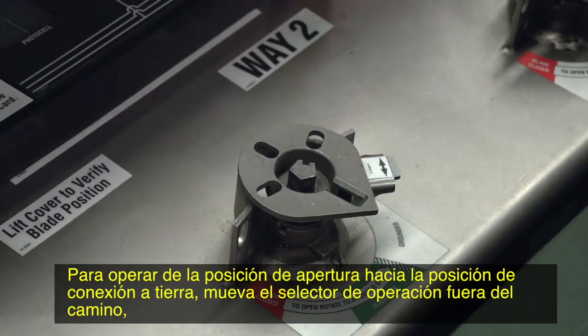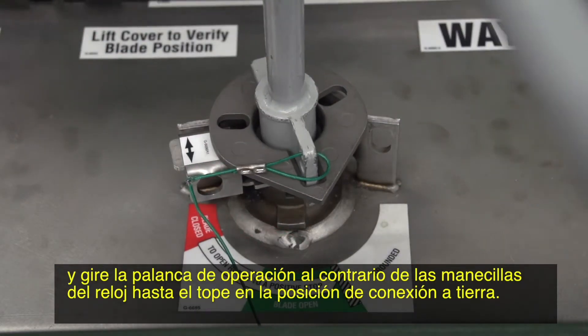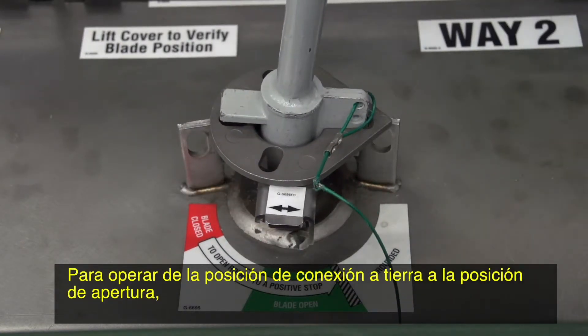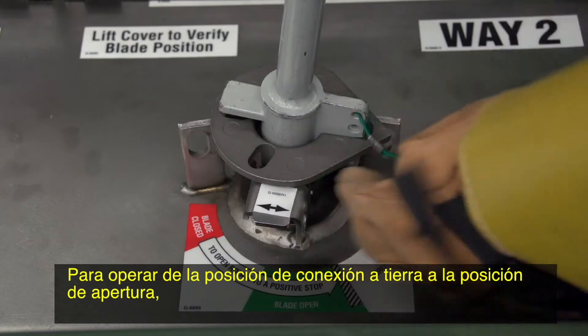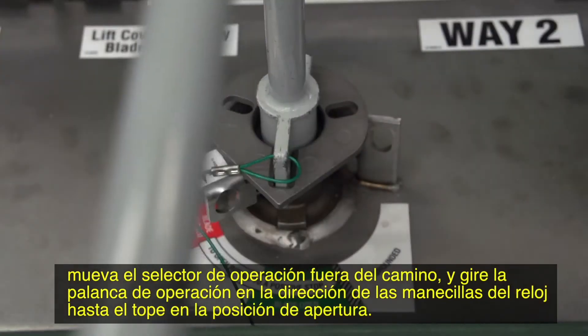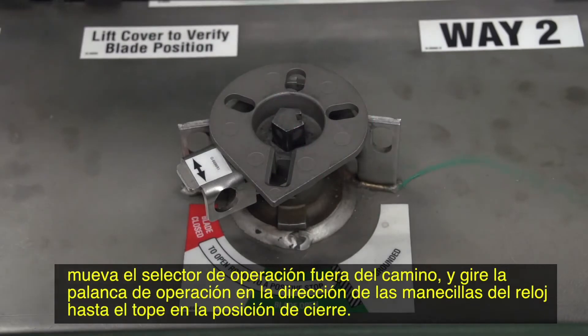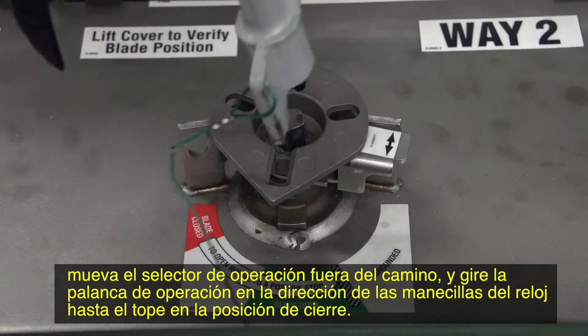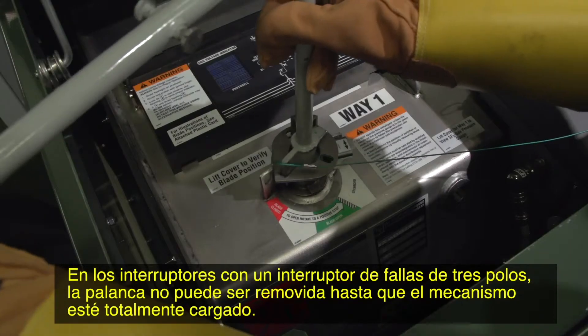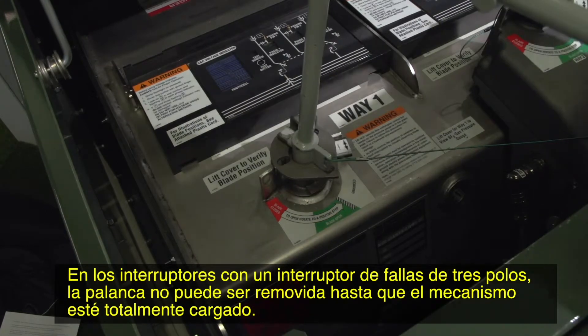To operate from the open to the grounded position, rotate the selector out of the way and rotate the operating handle clockwise to a stop in the grounded position. To operate from the open to the closed position, rotate the selector out of the way and rotate the operating handle clockwise to a stop in the closed position. On switches with a three-pole fault interrupter, the handle cannot be removed until the mechanism is fully charged.